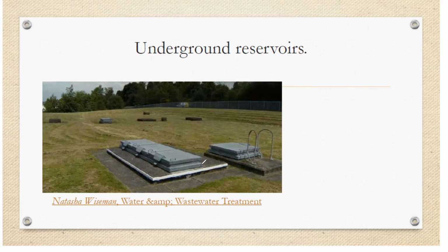So why? Because GSR is simply for storage, simply for storing the maximum quantity, and for ESR we need to provide the water to the public by gravity with optimal pressure, and hence ESR needs to be constructed.